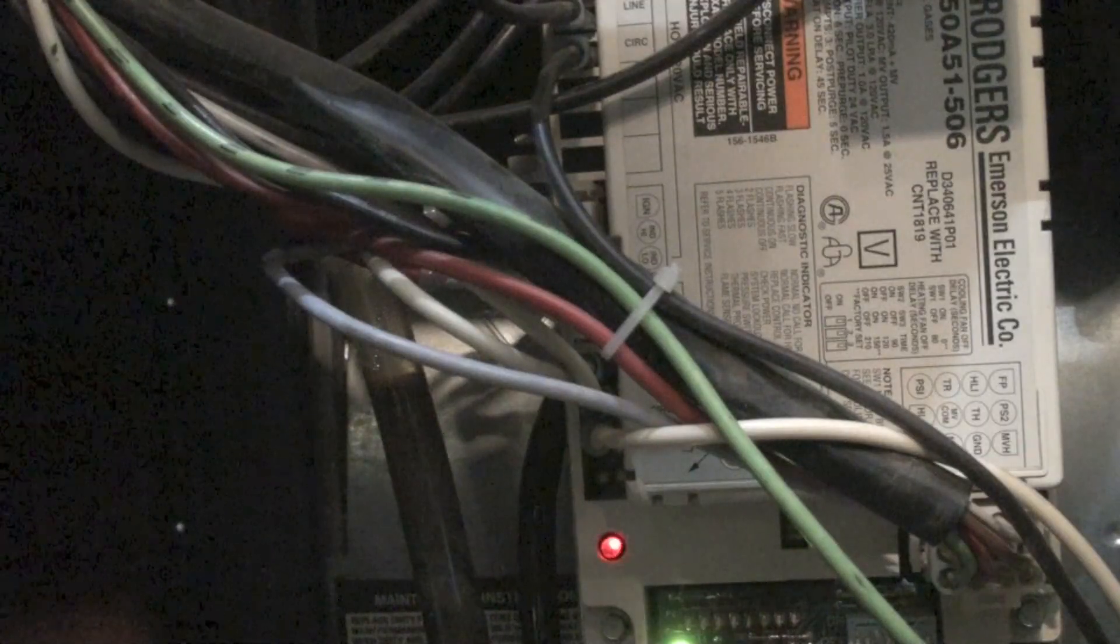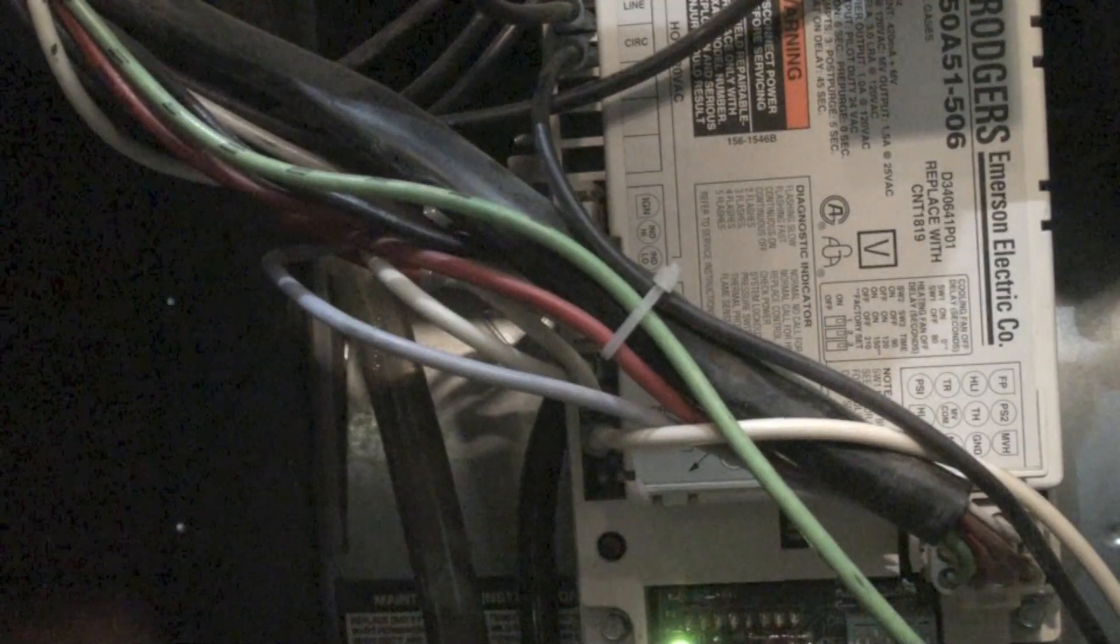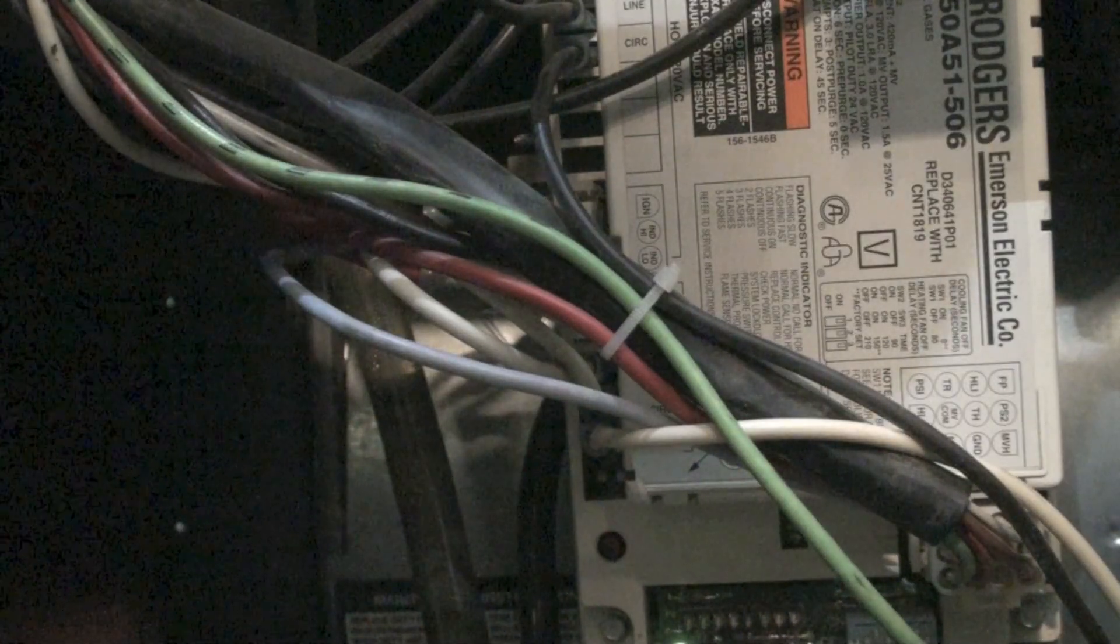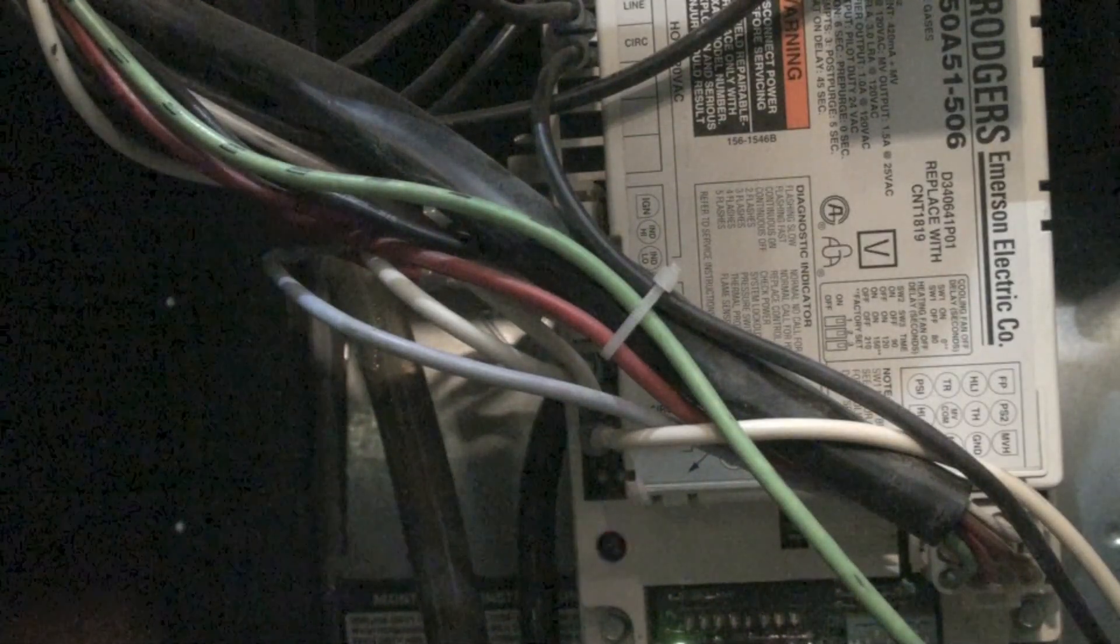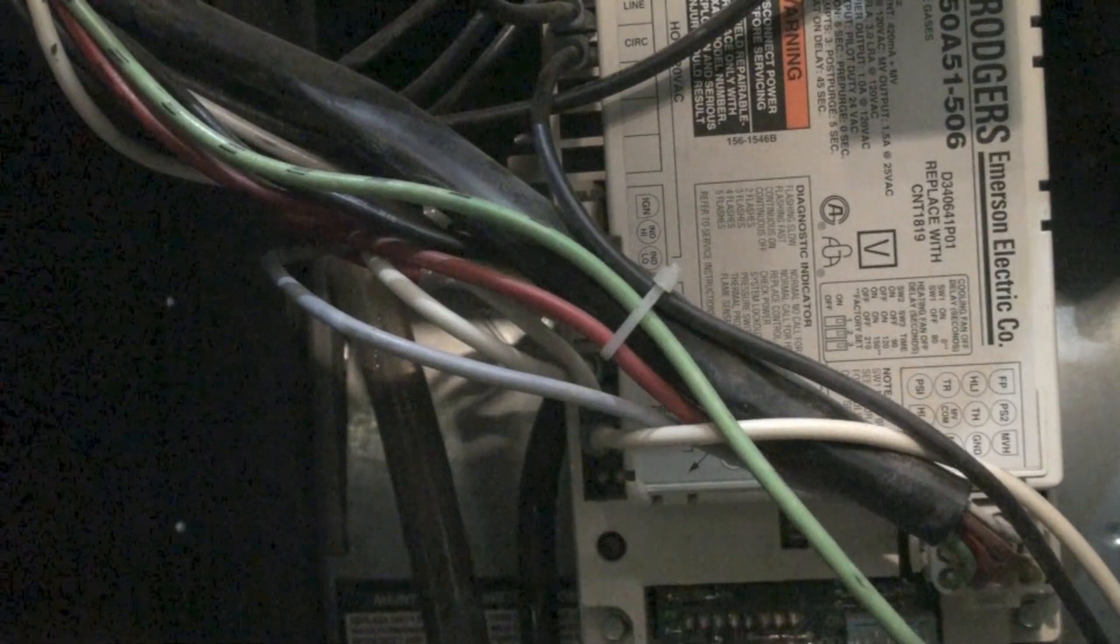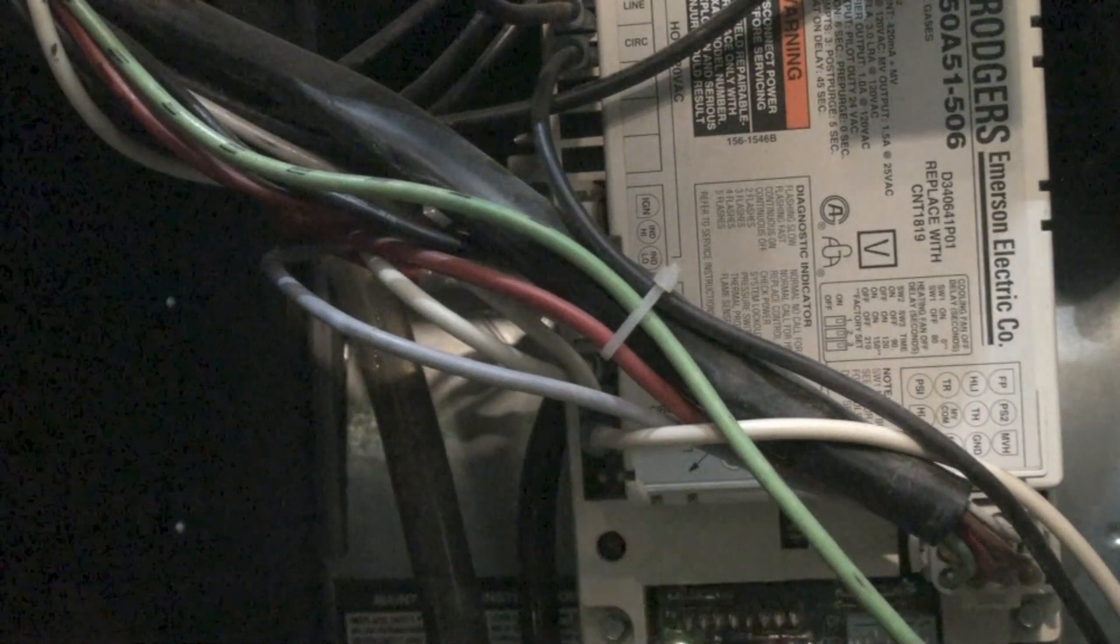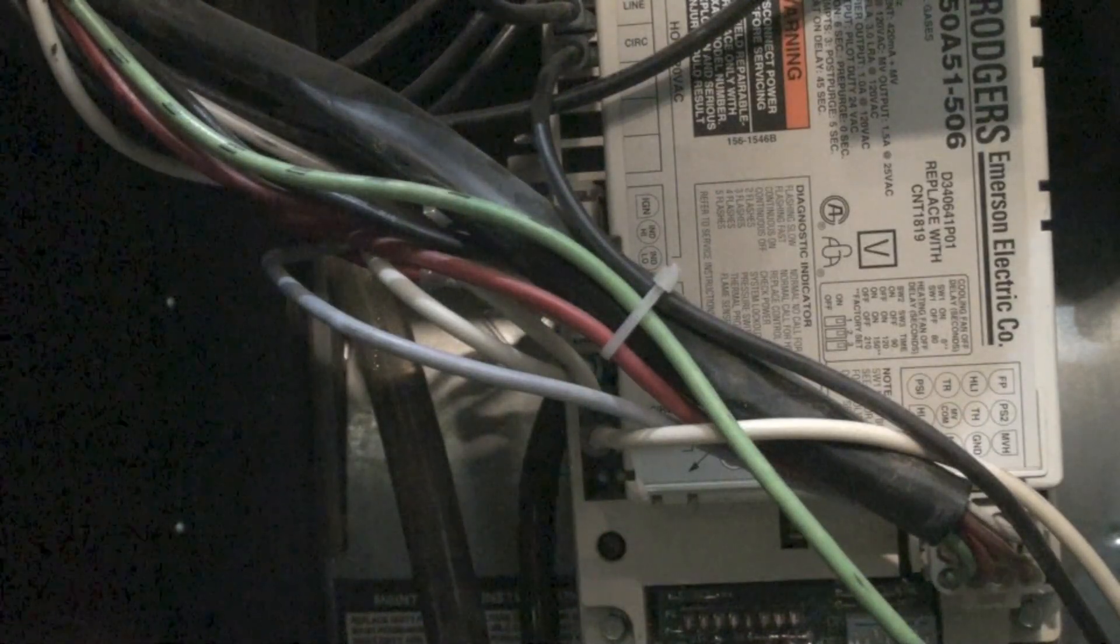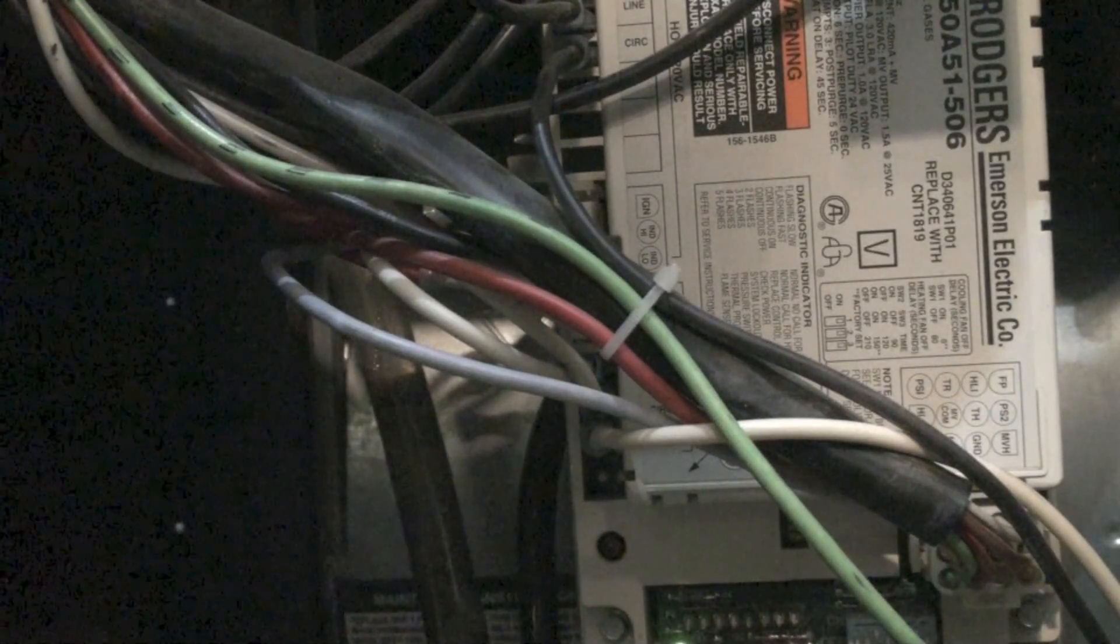Okay, this is a two blink code. Two blinks and a pause. That's flame failure. For some reason the flame was not lit. So this could be gas supply, this could be a flame rod not sensing flame, hot surface igniter's broken, number of things like that. Start with a simple one: flame rod probably needs to be cleaned. So that is flame failure.